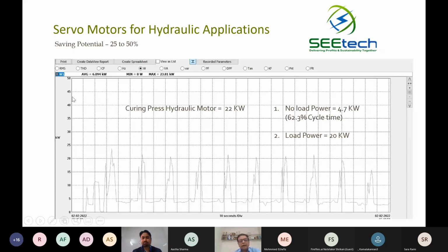So when a load analyzer was put onto the motor, the actual situation comes out very clearly, and it's a 22 kilowatt motor. So what is the problem statement? The problem is that we are having a fixed loss. If a motor of higher efficiency is used, these peaks will be minimal, and overall power consumption will reduce, but the peak occurs for a much lesser period of time.